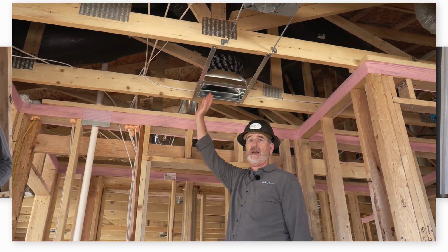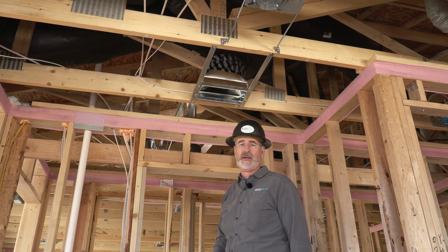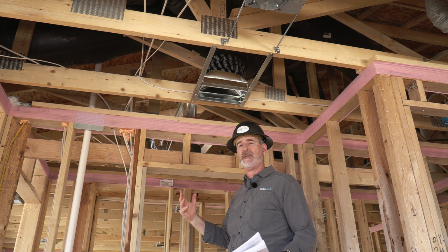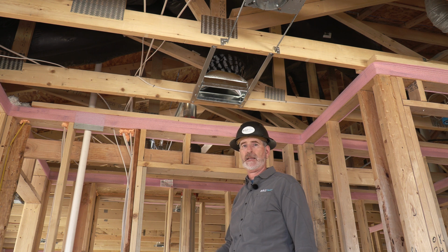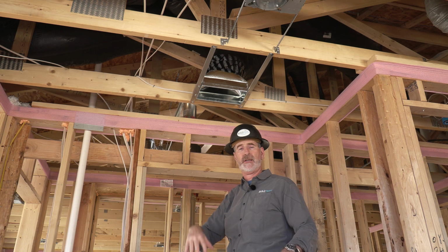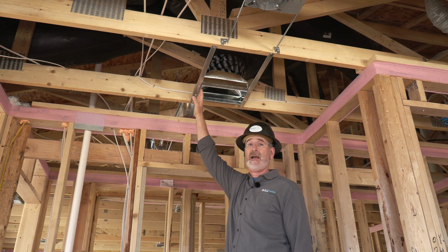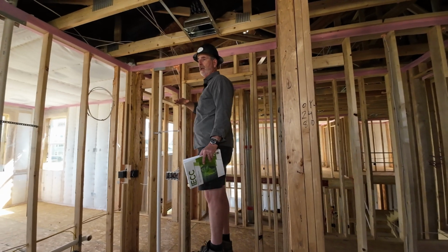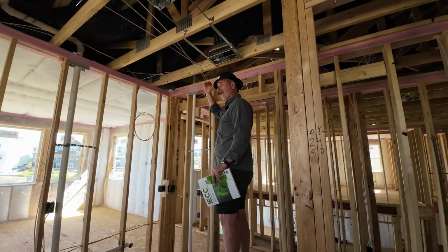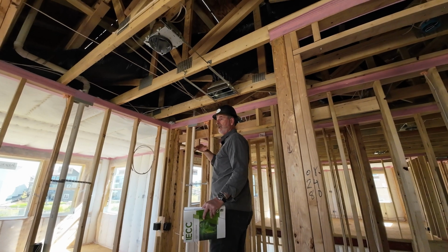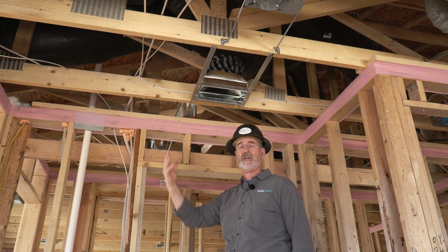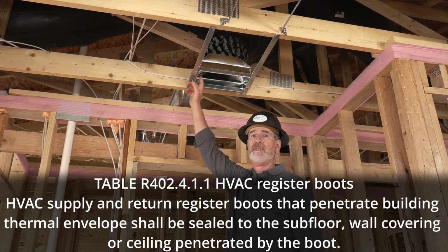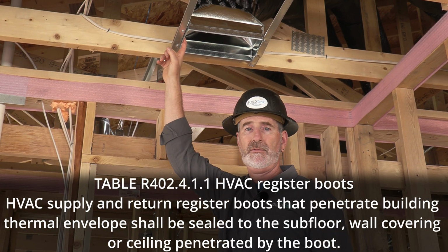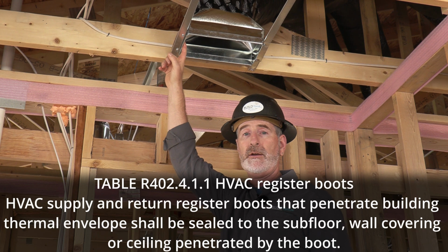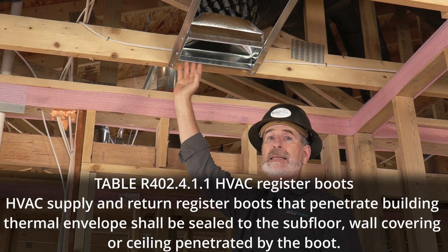I wanted to talk about duct boots and when they're penetrating the building thermal envelope. So in this case, we have a duct system in the ventilated attic, and the duct boot is supplying air to the conditioned space. So it's going to have to penetrate the drywall plane, which is our primary air barrier on the high side of the house that's separating conditioned space inside the house from unconditioned space up there. So whenever you have a duct boot that's penetrating the building thermal envelope, either of the primary air barrier systems there, it needs to be sealed to that surface that it's penetrating.